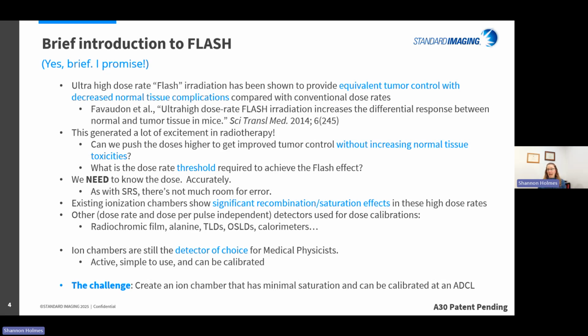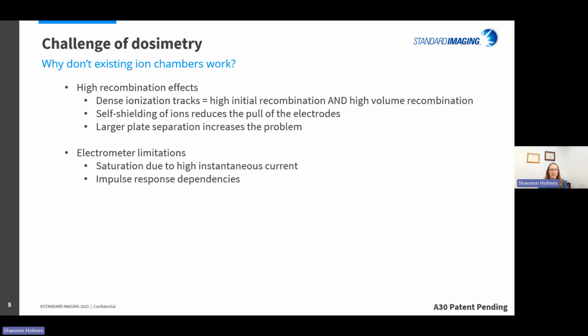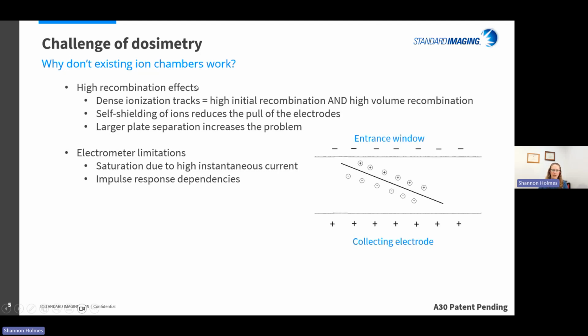But most of all, they can be calibrated at the national or at the dosimetry calibration labs so that you can get values that are NIST traceable and really trust that you're measuring dose accurately for these beams. So the challenge for us was, can we create an ion chamber that has minimal saturation and can be calibrated at an ADCL? The general challenge of dosimetry in terms of the function of ion chambers, why the current ones don't work very well, really centers on that high recombination.